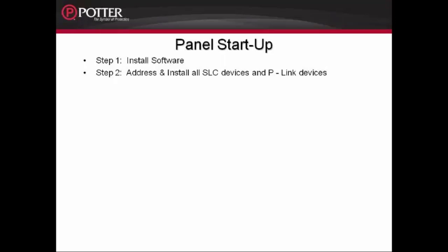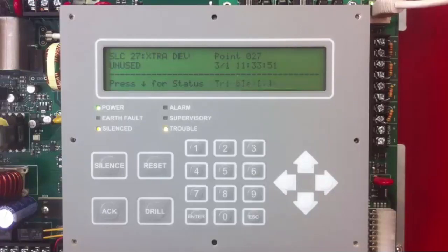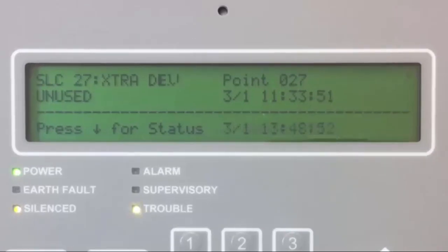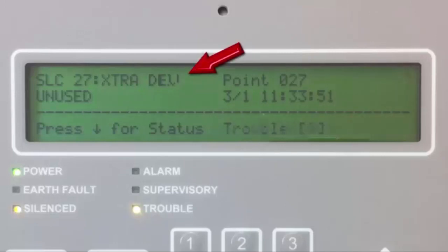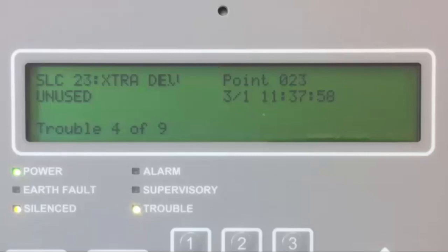Step 2: Address and install all SLC devices and P-Link devices. For detailed information on the SLC devices, the P-Link devices, and how to address them, please refer to Modules 3 through 6. Once you have them addressed and connected to the SLC circuit and the P-Link circuit, you will have several troubles on the Fire Alarm Control Panel. The number of SLC devices connected should match the number of troubles you see on the LCD screen. The trouble indicated by a device connected to any of the SLC circuits, which is not programmed into the system, is an extra device. This is a good troubleshooting tool.